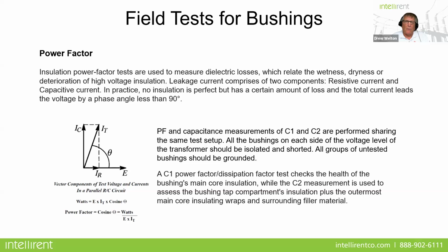Okay, current in a bushing is comprised of two components: you have a resistive current and a capacitive current. In practice, no insulation really is perfect, but it has a certain amount of loss, and the total current leads the voltage by a phase angle less than 90 degrees. Again, it's just basic fundamental power factor knowledge. Power factor and capacitance measurements of both your C1 and C2 are performed sharing the same test setup. All the bushings on each side of the voltage level of the transformer should be isolated and shorted. All groups of untested bushings should, of course, be grounded.